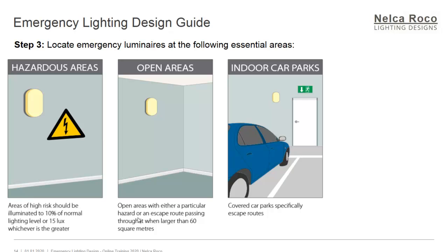For open areas — areas with either a particular hazard or an escape route passing through them — when larger than 60 square meters, you should have a dedicated emergency fitting for that open area. For indoor or covered car parks, escape routes should specifically have a dedicated emergency fitting.